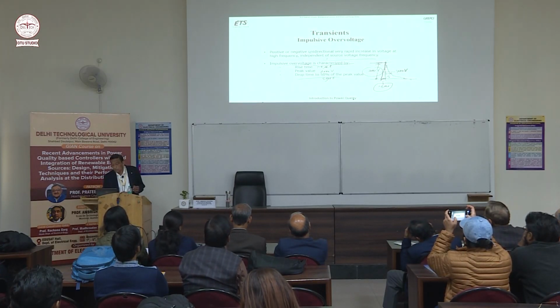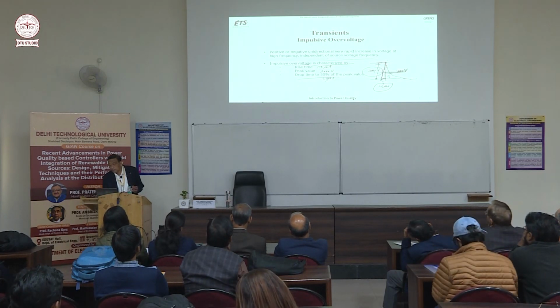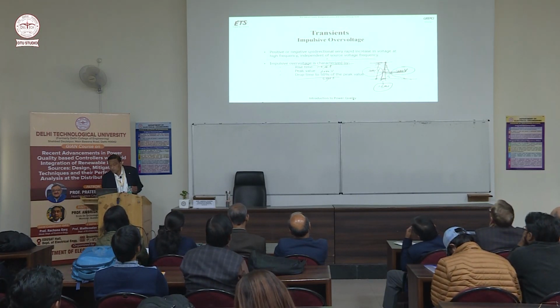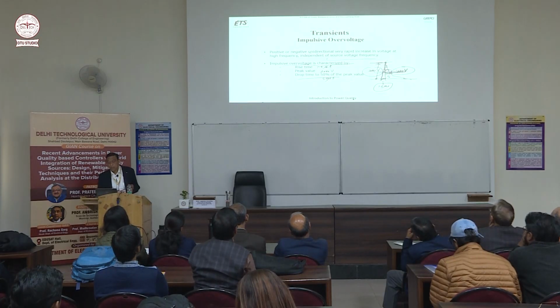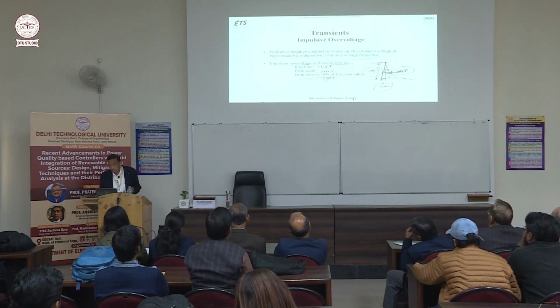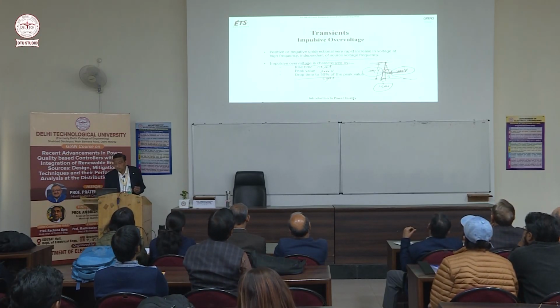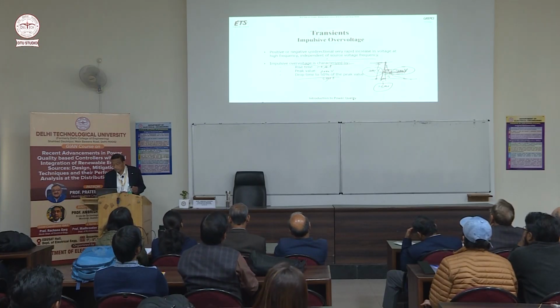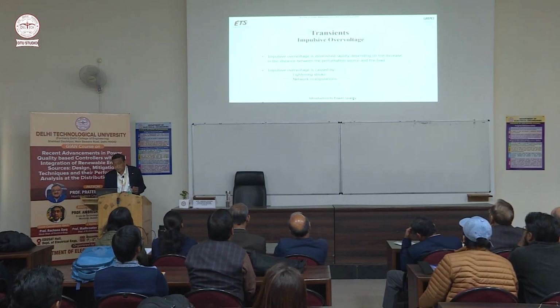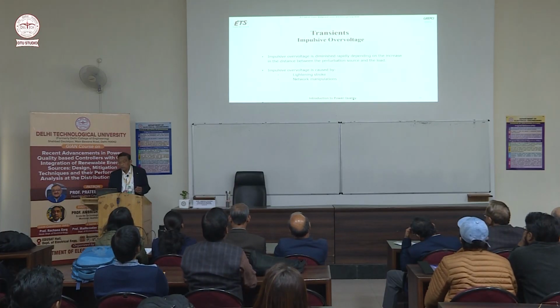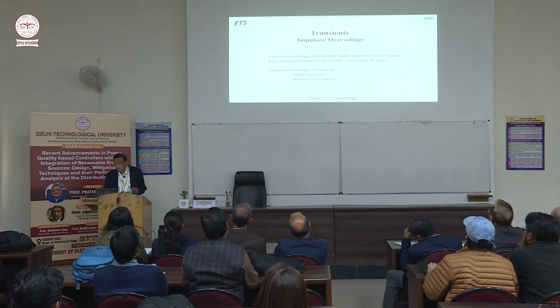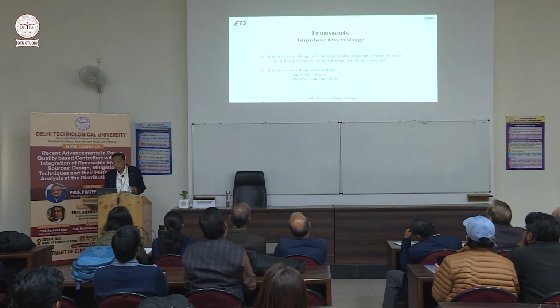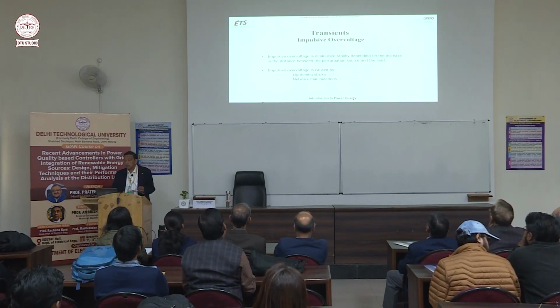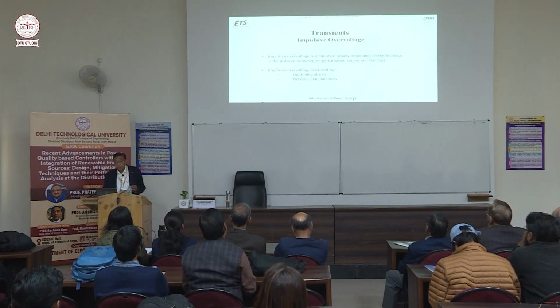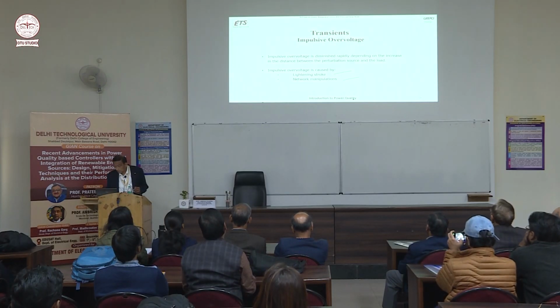And drop time to 50% off. 50% means 1000 volt. So here you can say this is the drop time up to 50% of peak value, maybe 50 microsecond or something, that depends. Impulsive over voltage is diminished rapidly depending on the increase in the distance between the perturbation source and the load. Impulsive over voltage is caused by lightning stroke, network manipulations.